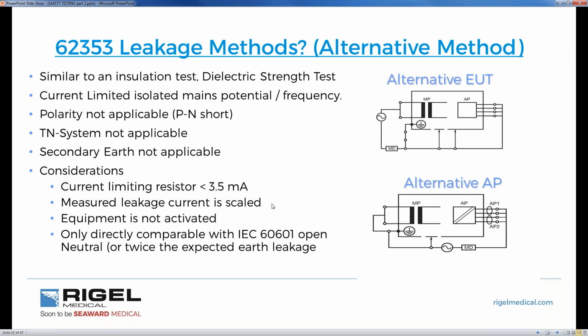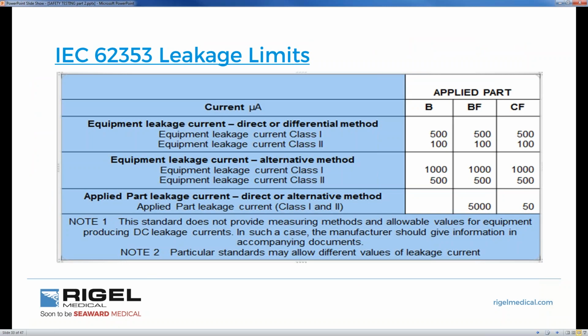The equipment isn't activated, it isn't powered at any time. A slight drawback is that you're not going to power any of the applied parts. The applied parts will be unpowered. Therefore, will there be any leakage present if you're not powering them? Highly unlikely. And it's only really directly comparable with the 60601 open neutral. And we'll look at the comparisons in the next couple of slides.